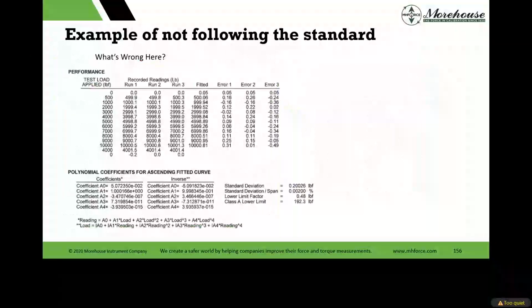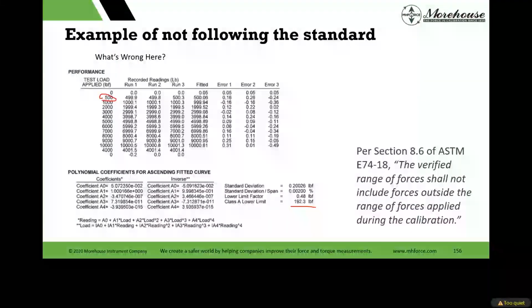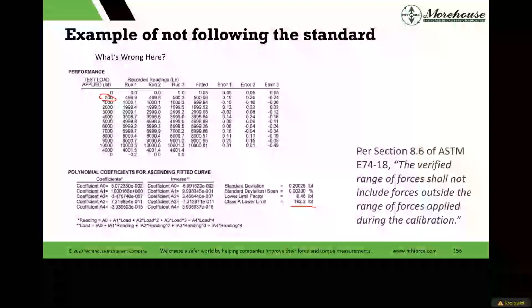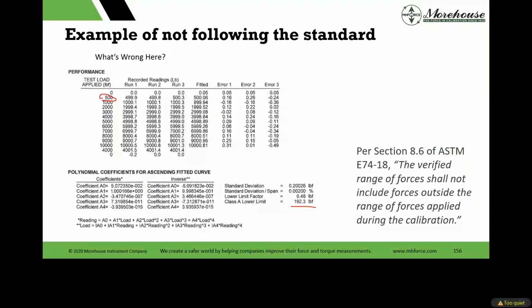So what do we see happening in the field? Here's an example of a cert from one of our competitors. Class A lower limits, 192.3. First force point is 500. That should never happen. This says basically shall not include forces outside the range of calibration, and the first force cannot be less than 400 or 2000 times the resolution.